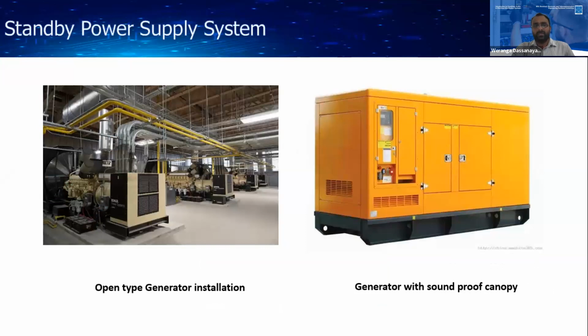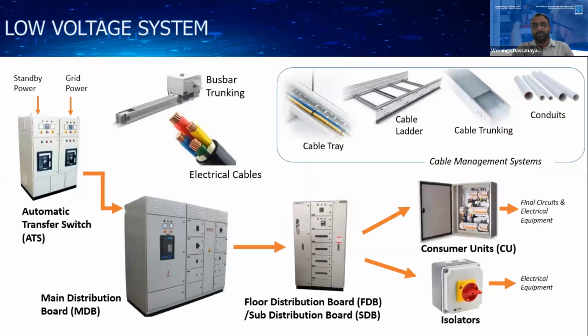When we talk about a standby power supply system, there are basically two types available. One is the open type generator, and the other is the soundproof canopy type. In most sites, you have seen generators with soundproof canopies, and there are also open type generator installations, which operate as parallel synchronized systems, mostly in larger scale installations. When you go to the low voltage system, the first point is the automatic transfer switch or manual changeover, which I mentioned earlier. There are two incoming supplies there. The first is the main power source, and the other is the standby power system.